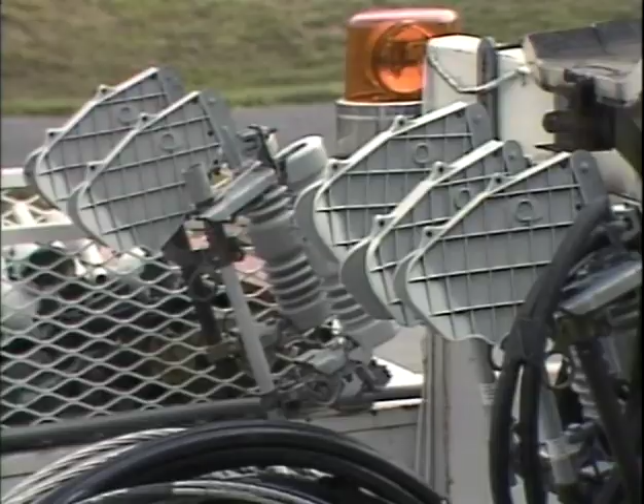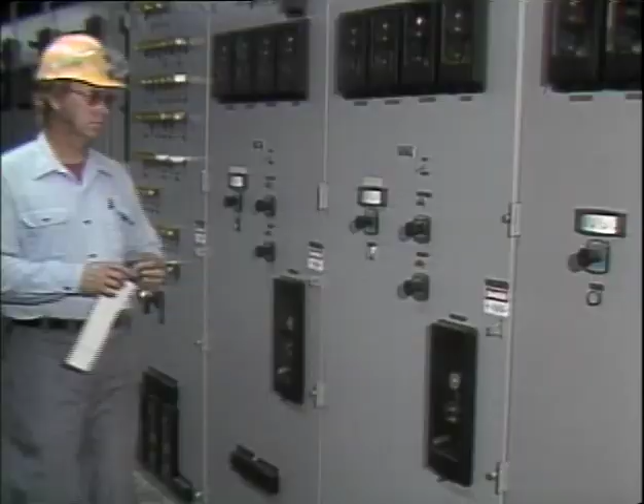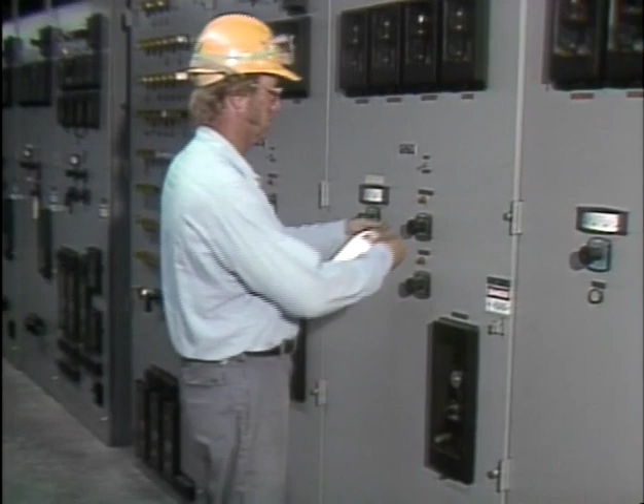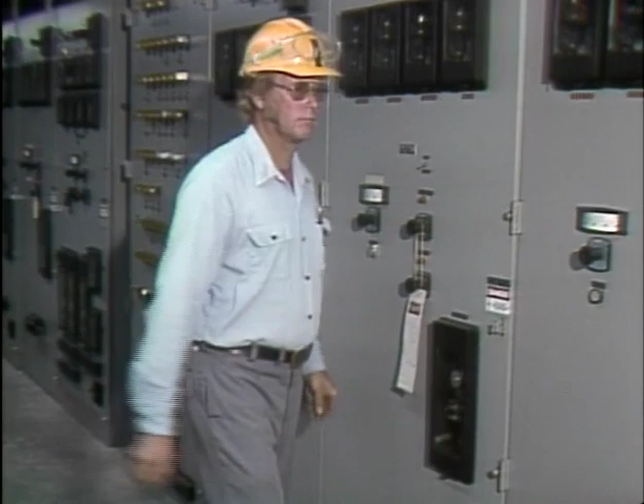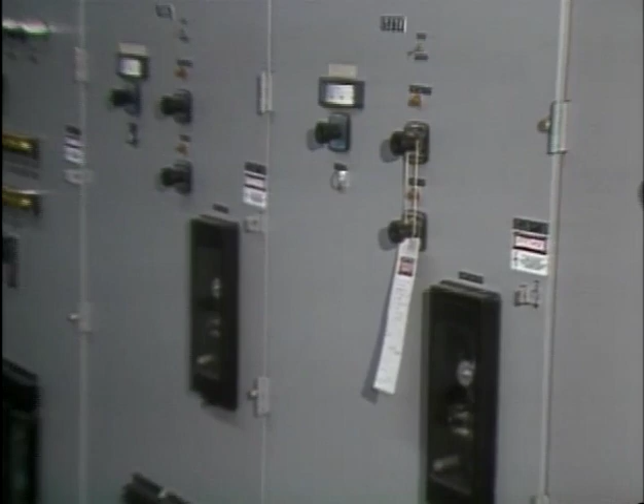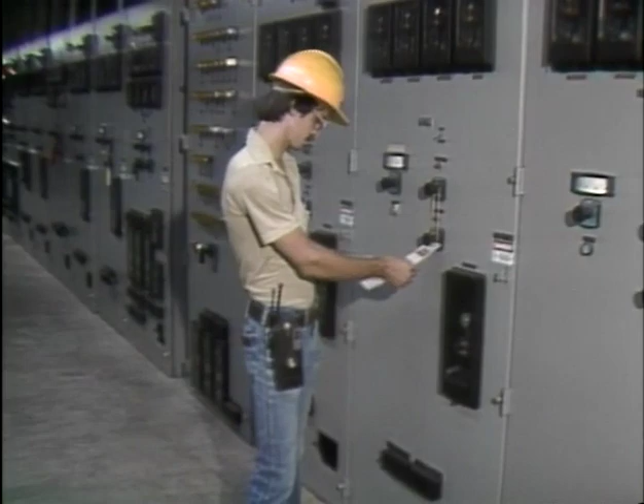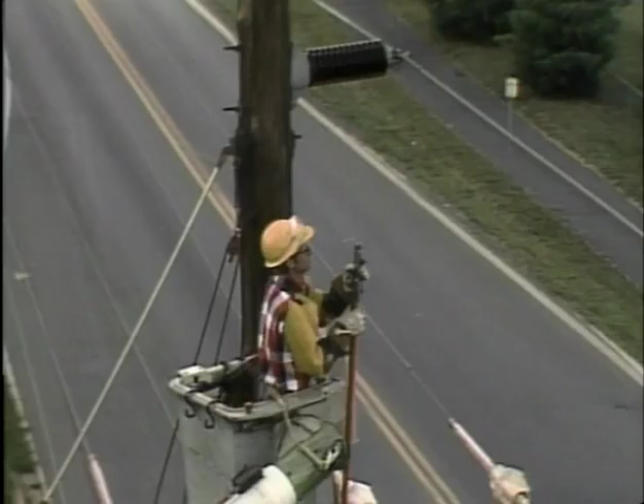Whenever you open a switching device, whether it be a disconnect switch or a circuit breaker, you should place a tag on the device. Tagging protects workers by letting others know the status of a circuit. For example, if you opened a breaker to de-energize a circuit for repair work, the circuit must remain de-energized until the work is completed. A tag lets others know who's working on the circuit and why. Most important, the tag also serves as a warning that the breaker must not be closed. Closing the breaker would, of course, energize the circuit and endanger anyone working on the circuit.